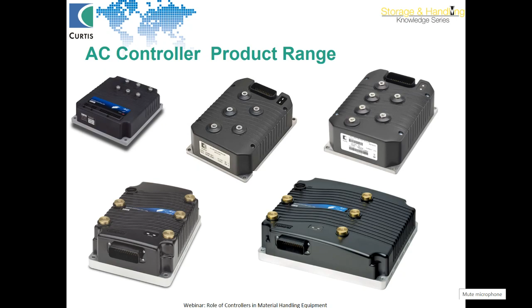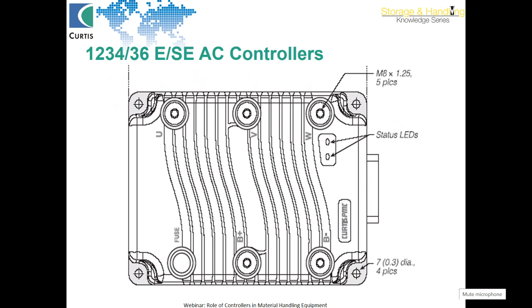This is the typical controller picture, in which you can see the top three terminals are the U, V, and W motor phase control power terminals. On the bottom side, you have the power connections coming from the DC, that is the battery side, which is B positive and B negative. Below the top right, you have two status LEDs. They will blink in a different pattern for every single fault. You can count the number of blinks and know what fault the controller is showing. Refer to the manual, and you know the meaning of the fault and the process of troubleshooting it. On the right hand side, there is a 35 pin AMP sealed connector, which imparts IP65 ingress protection to the controller. And there are four mounting bolts of M8 size in larger controllers and M6 size in the smaller controllers.